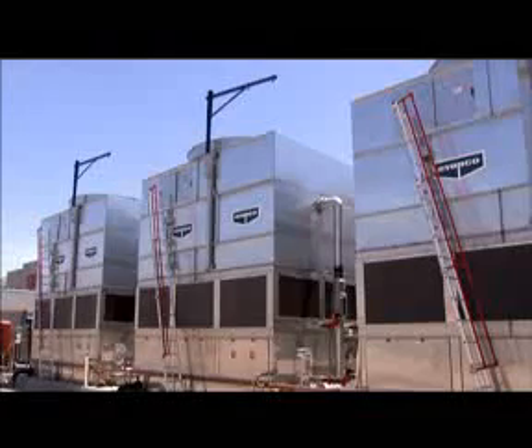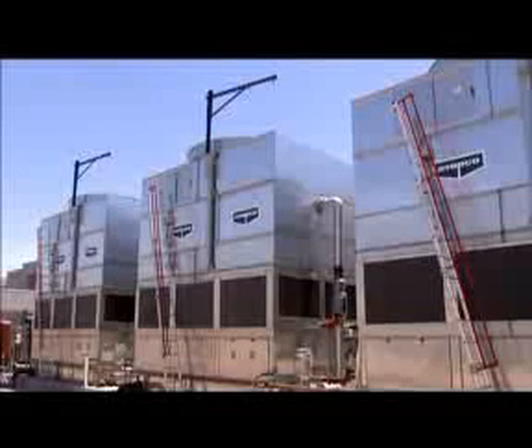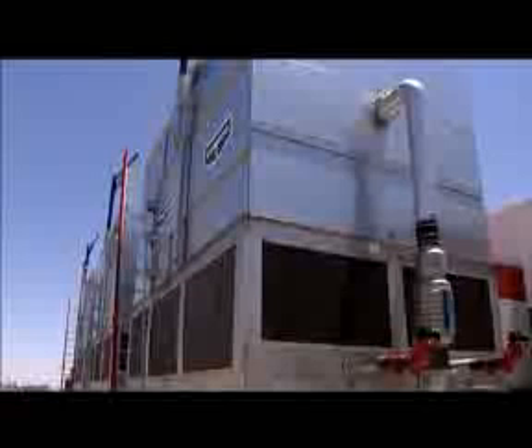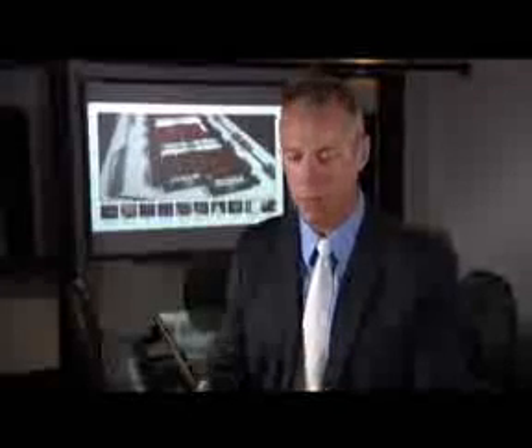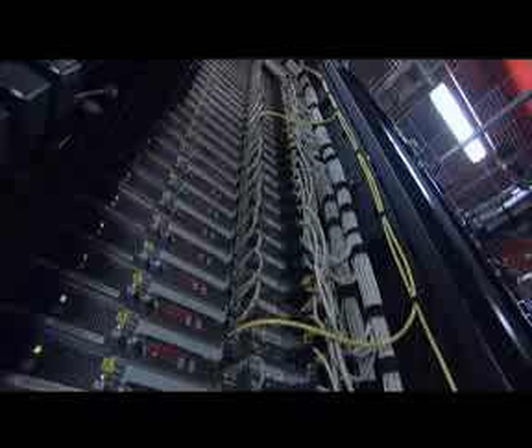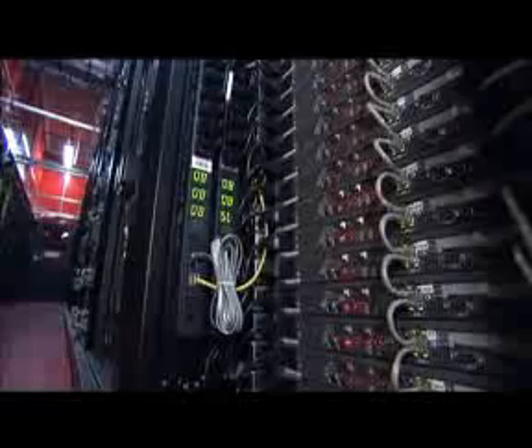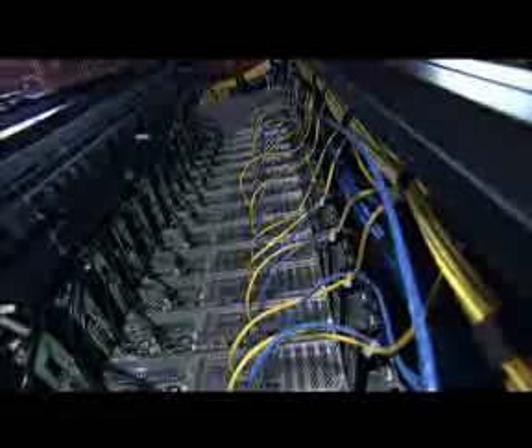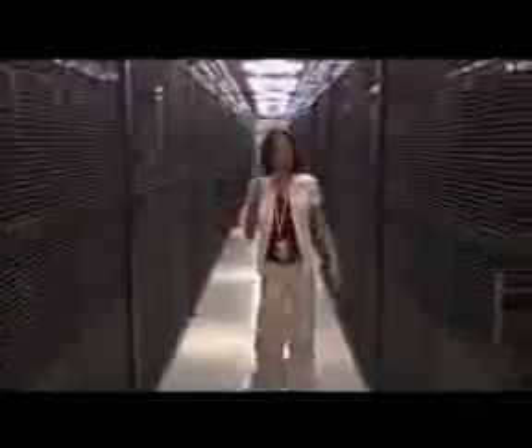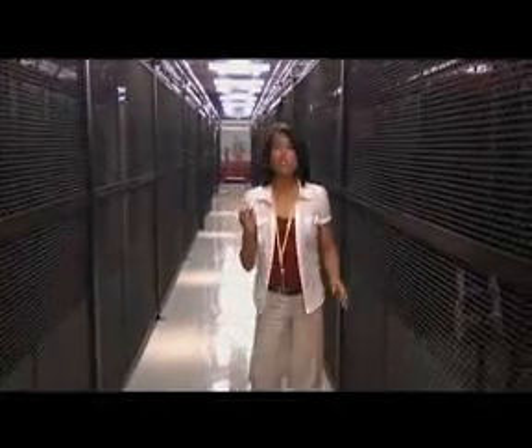And that gives them flexibility with respect to how much cooling capacity they add, which is critical when dealing with ever-increasing and unpredictably dense heat loads. A natural tendency of a customer when they purchase a cabinet is to cram as much in there as possible. One unintended consequence is you need to design all new mechanical systems to handle this higher density heat load.